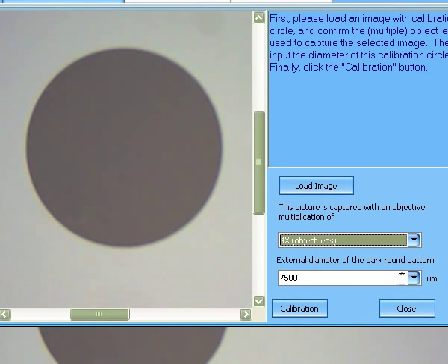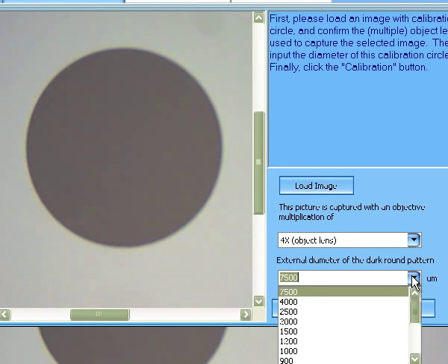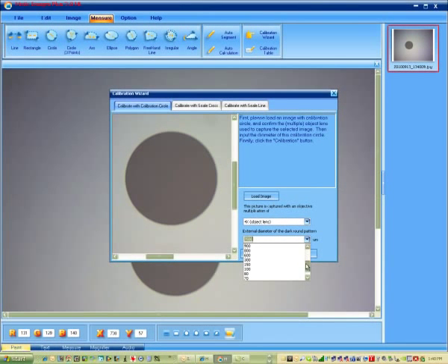Then select your objective lens. In this case, it's a 4x objective lens. The stage micrometer that we used is 0.6 millimeters, which equates to 600 micrometers.